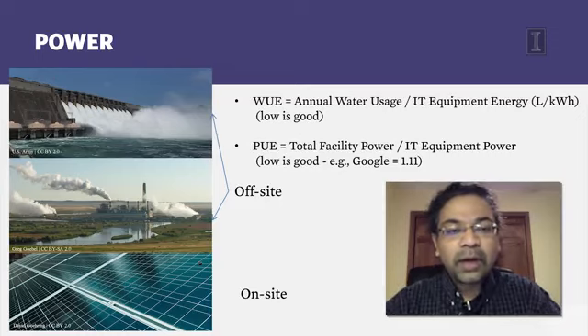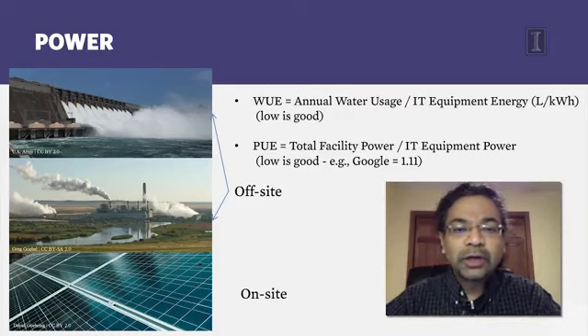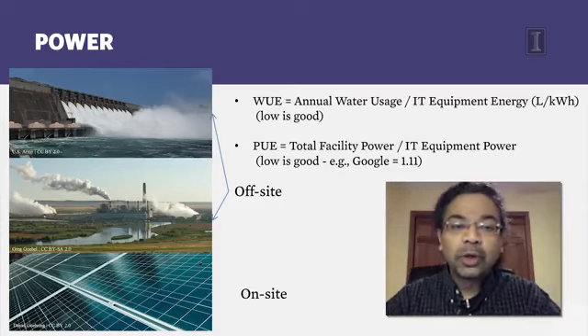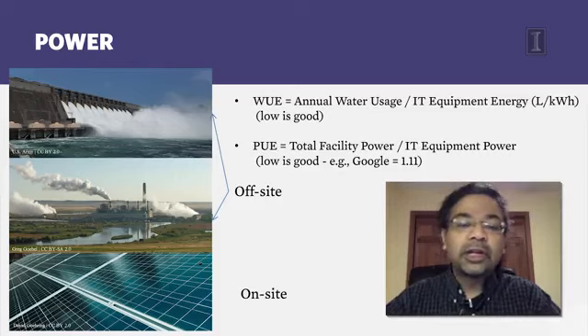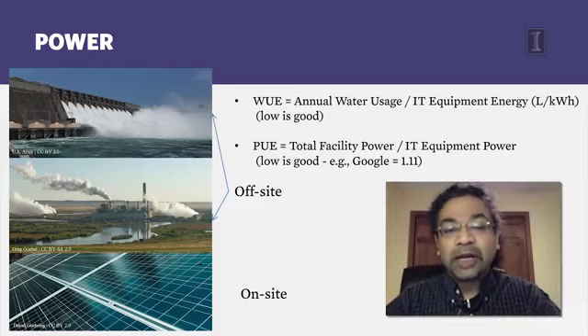There are a couple of important metrics used to measure the efficiency of data centers in terms of water and power usage: water usage efficiency (WUE) and power usage efficiency (PUE). WUE is the annual water usage divided by IT equipment energy, in liters per kilowatt hour—lower is better, meaning less water used per unit of energy. PUE is total facility power divided by IT equipment power—again, lower is better, since it means a larger percentage of incoming power is going toward servers, routers, and switches.